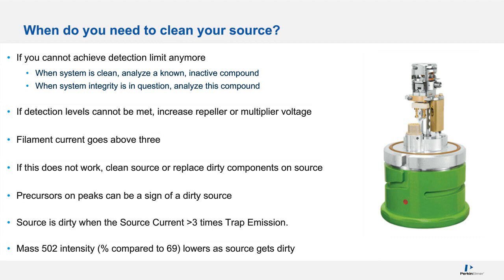I get this question, when do I know I should clean my source? Well, if you can't get your required MDL or reporting limit anymore, that's probably time that you need to clean the source. In our mass spec, the filament current, if it goes above 3, that's indicative the source is getting dirty. Okay. I say some stuff later on in the presentation about this as well. If mass 502 intensity is getting lower, that is also indicative that the source may be getting dirty.